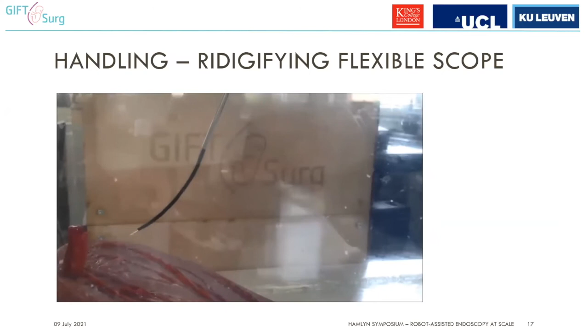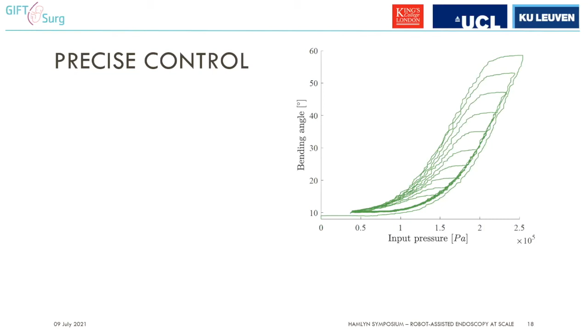So we encountered quite some hysteresis in there. You see here a typical pattern of hysteresis. You have an input signal, and then if you change direction, your output signal is not properly following. So there is kind of a delay, and that can lead to overshoots and severely hampers the usability of your system. That comes from several factors, but in general, in flexible instruments and catheters, you will always have this hysteresis problem. You have actuation, friction, and nonlinear behavior of material, all contributing to this.